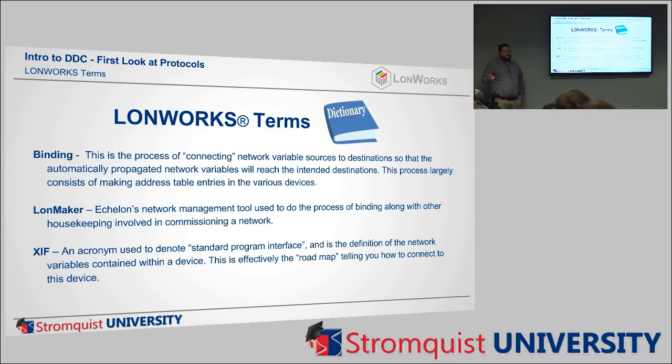And so you can do a flat LON system, and flat LON systems work, but then you're tied to flat LON from now on. So everything you do has to be LON. So if you buy a new boiler and it just has Modbus in it, you have to buy additional hardware to convert that to LON to get it into your system. And when you do LON in a Niagara system, it's a lot easier, and a lot more people can do it because it is easier. A flat LON system is a lot harder to engineer and program.